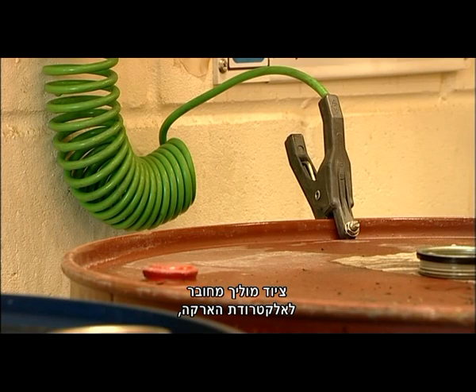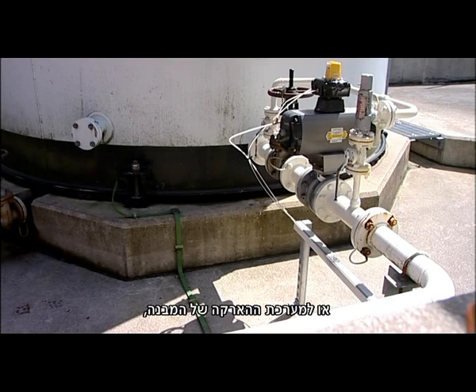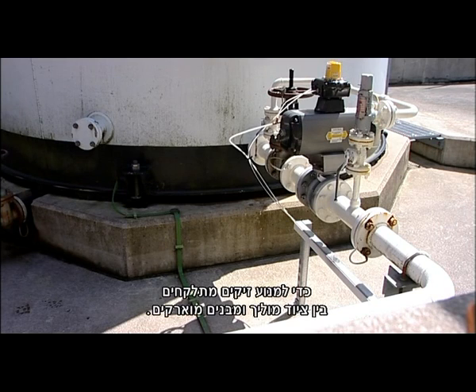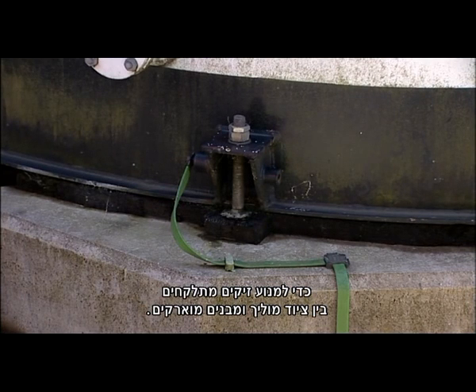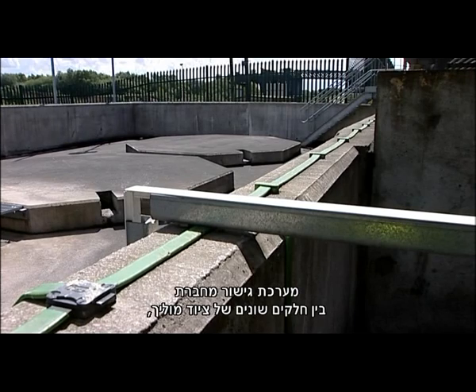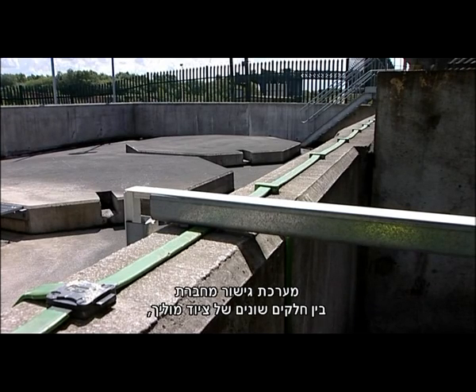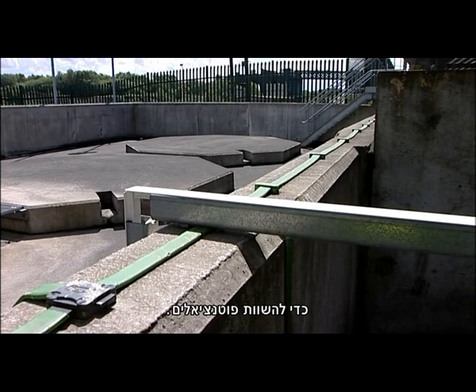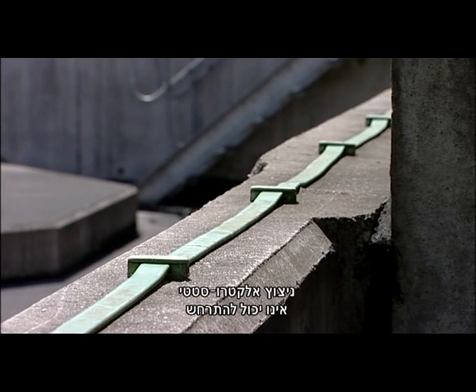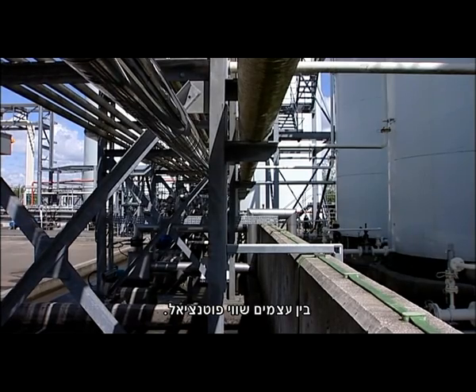Conductive equipment is connected to an earthing electrode or to the building earthing system in order to prevent sparking between conductive equipment and earthed structures. A bonding system connects various pieces of conducting equipment together to keep them at the same potential. Static sparking cannot take place between objects that are at the same potential.